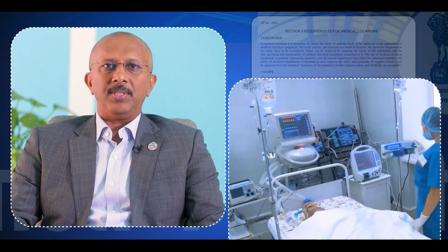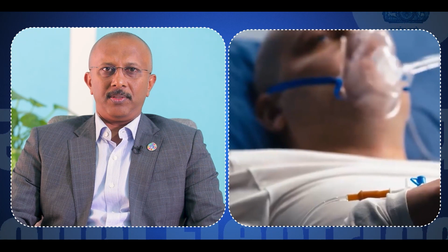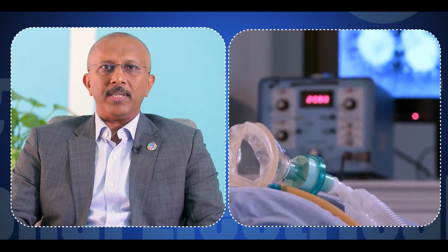For example, Section 9 of Part 3 explains medical locations, which is an area where patients are being treated. They are classified into Group 1 and Group 2 locations. In these locations, metallic objects or conductive fluids bypass the skin, and as a result, the chance of shock for the patient under treatment is much higher, so additional shock reduction measures are needed. Medical locations are also oxygen-rich areas, and sometimes highly flammable materials are present. As a result, Group 1 and Group 2 locations need special measures against ignition from fire as well.